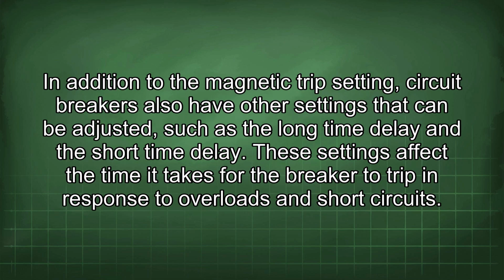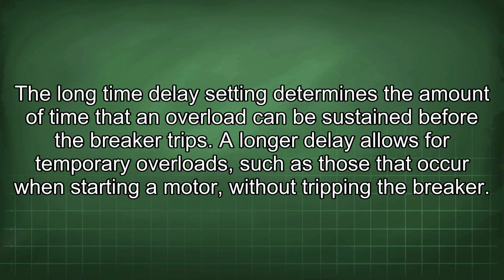In addition to the magnetic trip setting, circuit breakers also have other settings that can be adjusted, such as the long time delay and the short time delay. These settings affect the time it takes for the breaker to trip in response to overloads and short circuits. The long time delay setting determines the amount of time that an overload can be sustained before the breaker trips. A longer delay allows for temporary overloads such as those that occur when starting a motor without tripping the breaker.